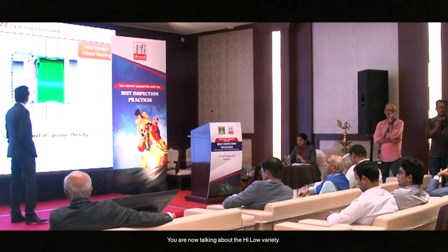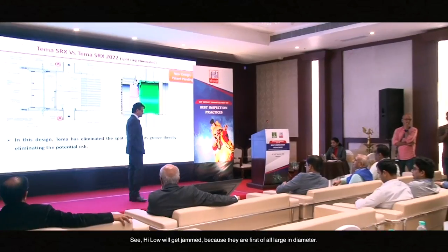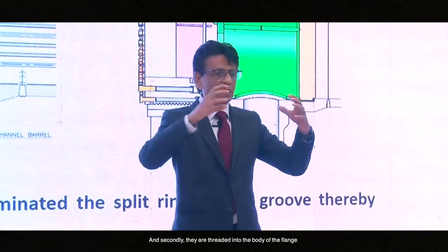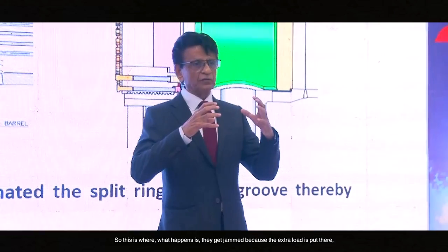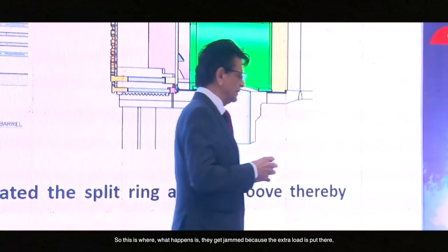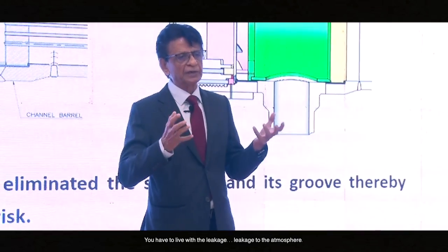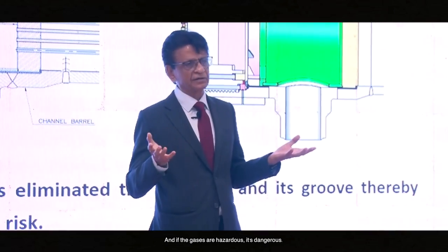Regarding the high-low variety: high-low will get jammed — the studs will get jammed because they are large in diameter and threaded into the body of the flange. The flange material is different from the bolt material; it is not a nut material. They get jammed because extra load is put there, galling takes place, and after that you just cannot remove it. You have to live with the leakage to the atmosphere, and if the gas is hazardous it is dangerous.